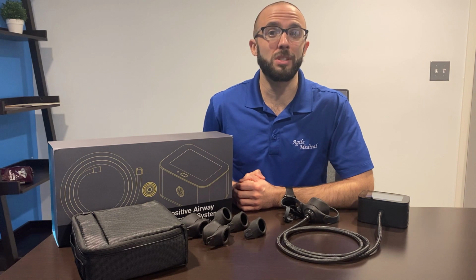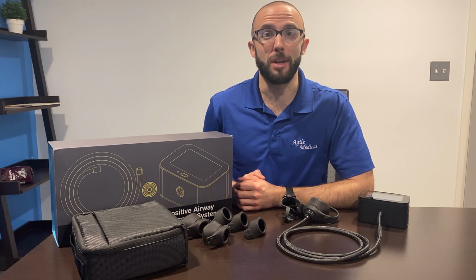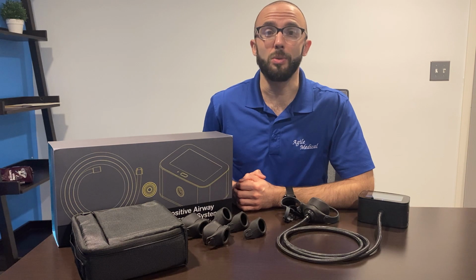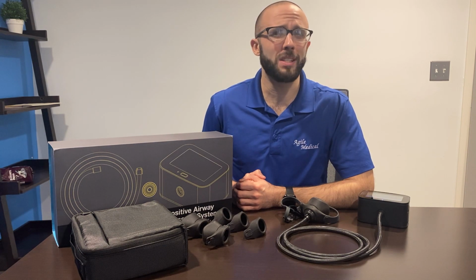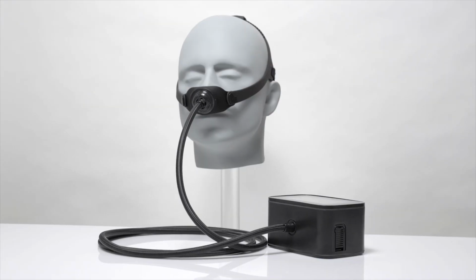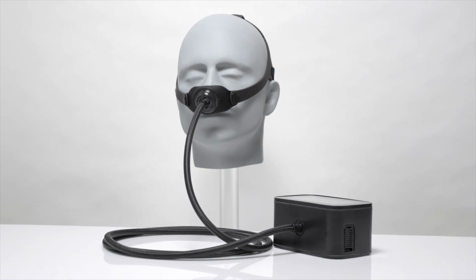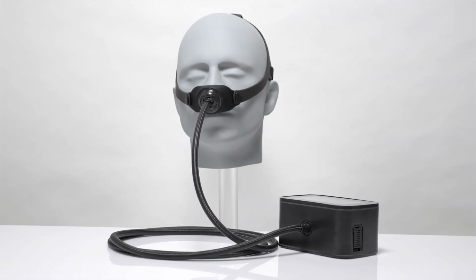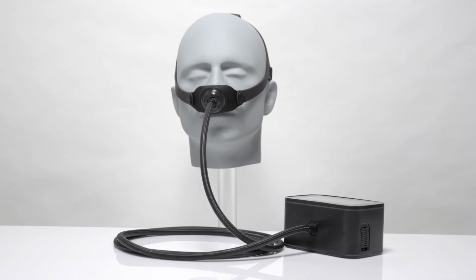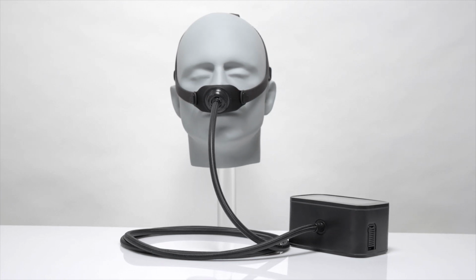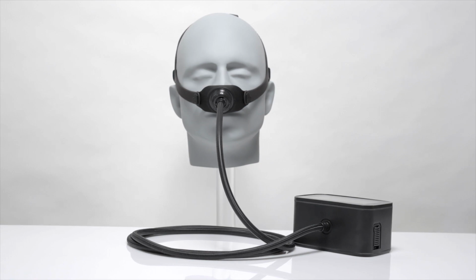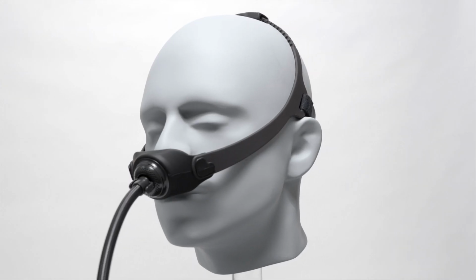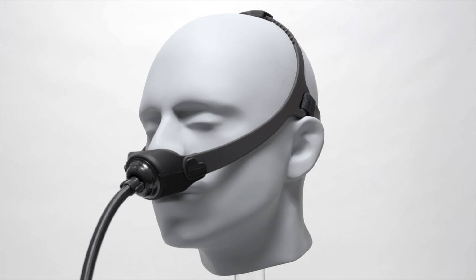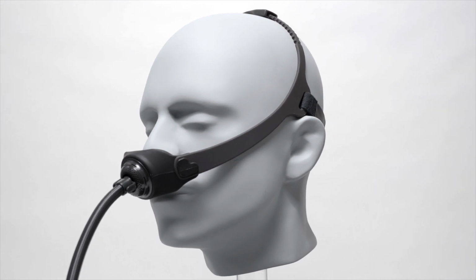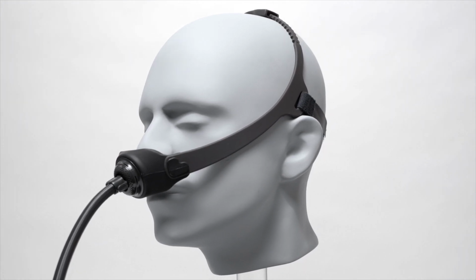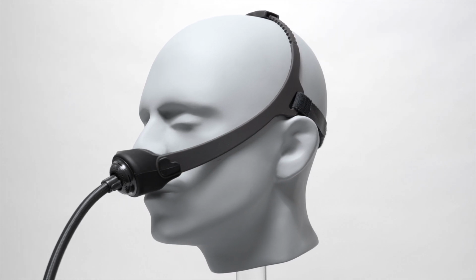The Somnera System was developed as an alternative for CPAP therapy for users who struggle with traditional CPAP. But what makes Somnera so different? Somnera is a low-flow system that mimics natural breathing cycles by only offering supplemental filtered air during inhalation. The device itself does not generate its own air pressure. The pressure used to keep the airway open is generated by the user's own breath. The innovative design of this system makes therapy much quieter, and less noise means a much more restful night's sleep for you and your bed partner.